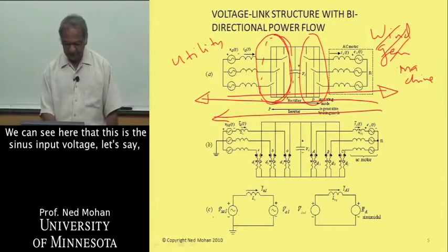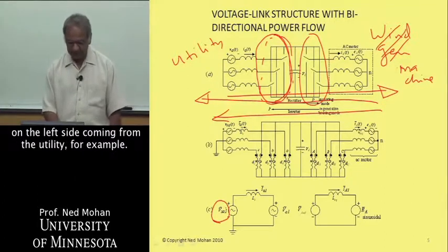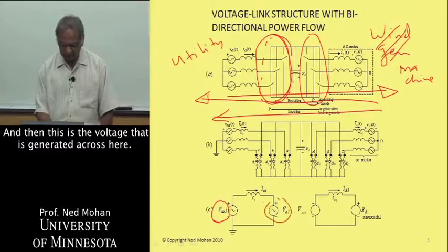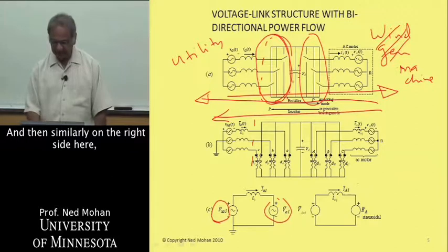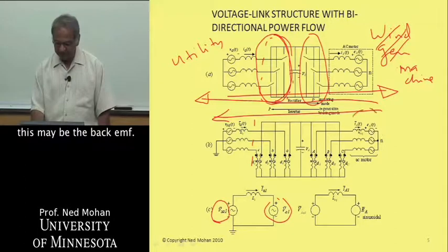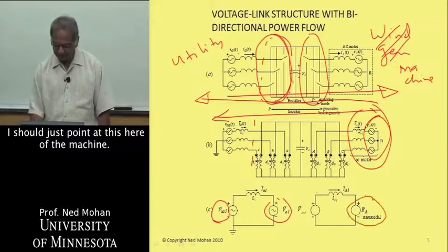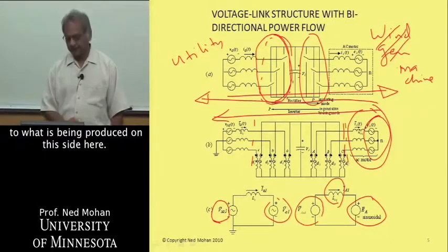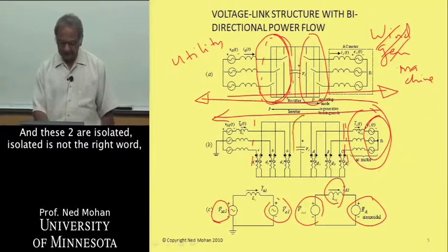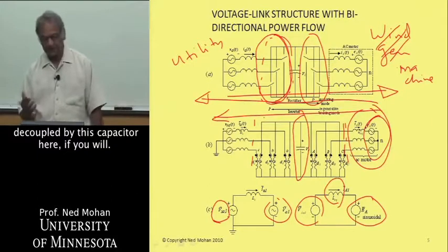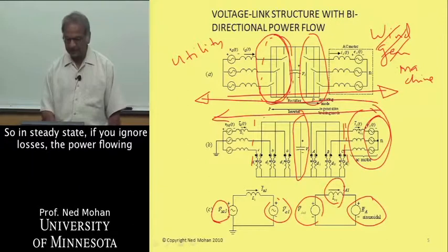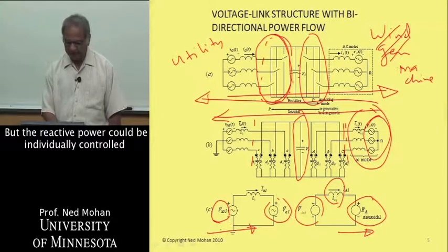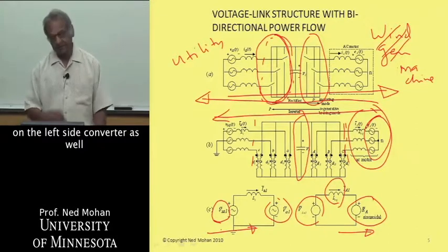We can also look at what happens on a per-phase basis on the left side and on the right side. This is the sinusoidal input voltage on the left side coming from the utility, for example. And then this is the voltage that is generated across here. Similarly on the right side, this may be the back EMF of the machine and then this inductance of the machine. These two are decoupled by this capacitor here. In steady state, if you ignore losses, the power flowing in has to be power flowing out, real power. But the reactive power could be individually controlled on the left side converter as well as on the right side converter.